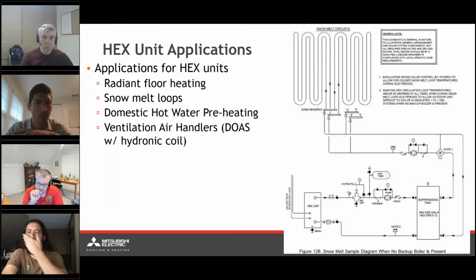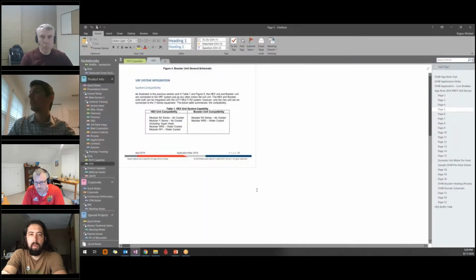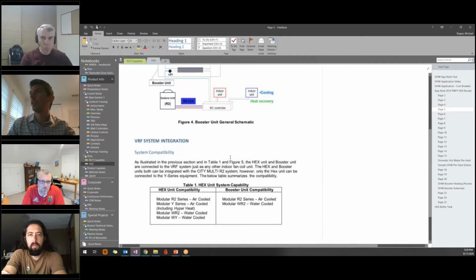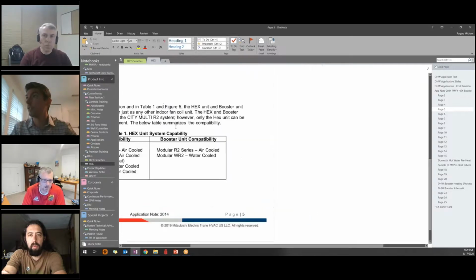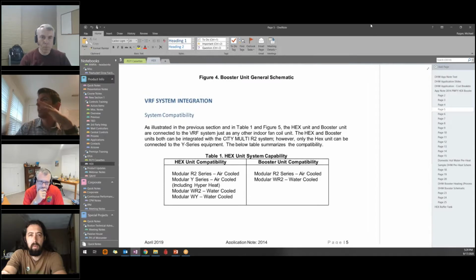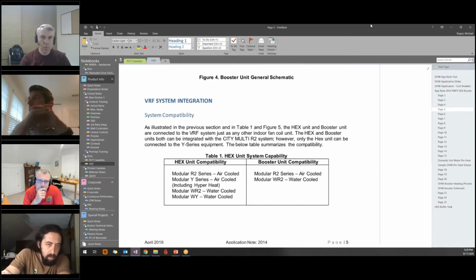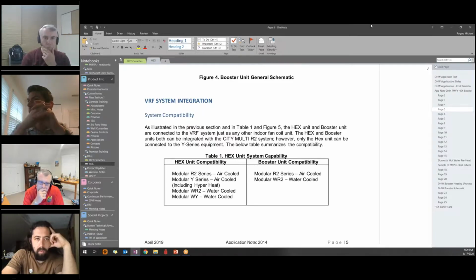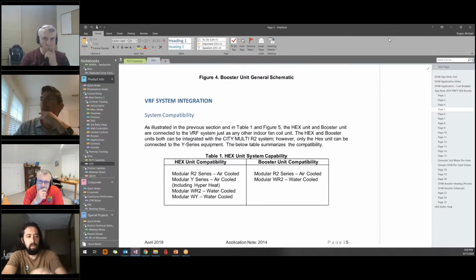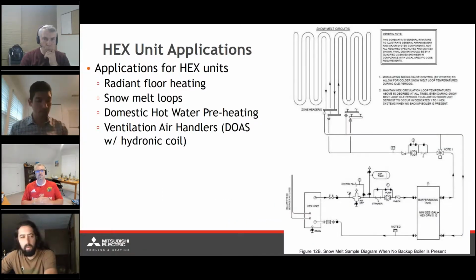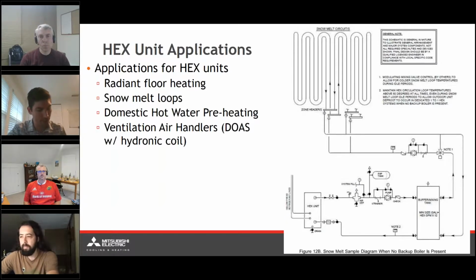Yeah, so I'm looking at the application note right now. Actually, I can bring this over here. I'll show everybody. In terms of VRF system integration, just reading off the page here: the HEX and booster unit are connected to the VRF system just as any other indoor fan coil unit. The HEX and booster units both can be integrated with the City Multi R2 heat recovery system. However, only the HEX unit, that's the HEX auxiliary unit, can be connected to the Y series equipment. That's the flexibility of the HEX auxiliary units: they can be connected to pretty much any three-phase equipment, as opposed to the booster unit, which is R2 equipment only. As to whether the units themselves have changed, I can look into that. I'm not entirely certain why that may have changed at this point, but let me dig into the rationale behind that.